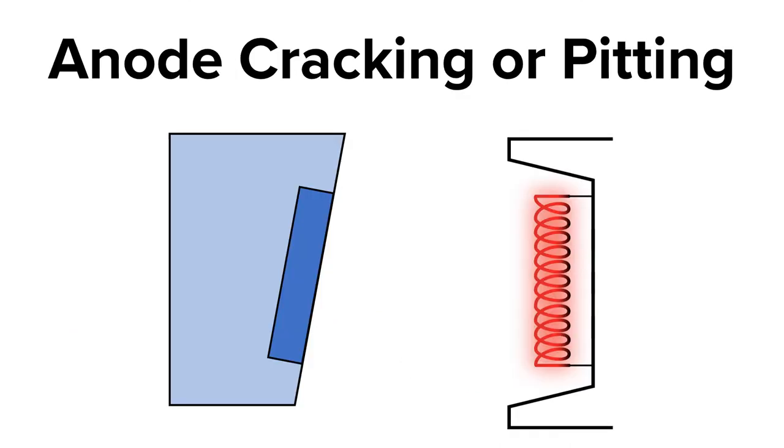Anode cracking or pitting causes total tube failure. There are a number of reasons why an anode will crack or pit. One reason is improper warming up of the x-ray tube.